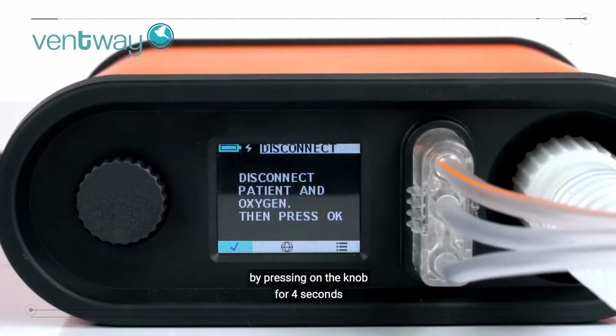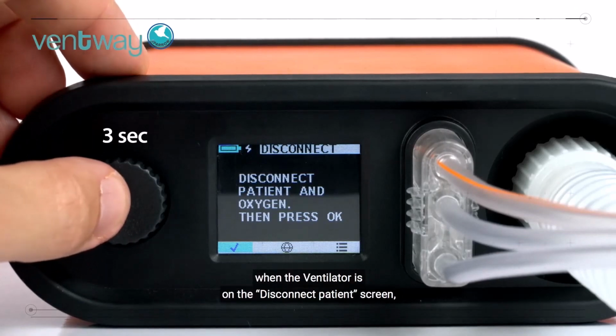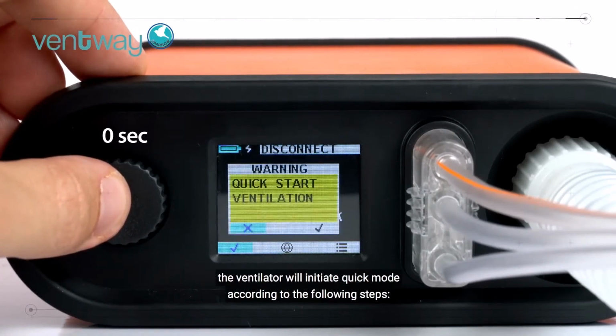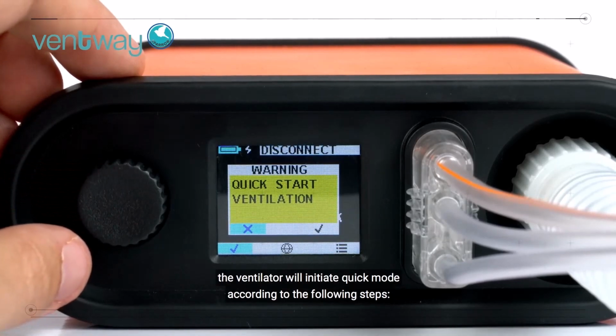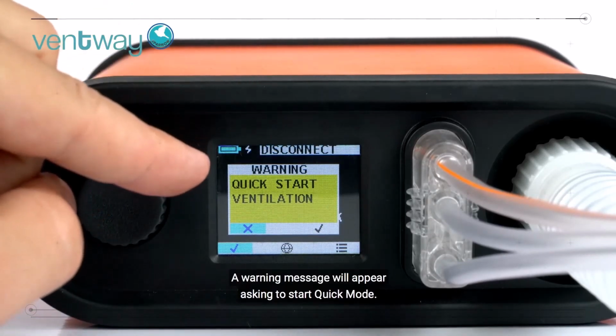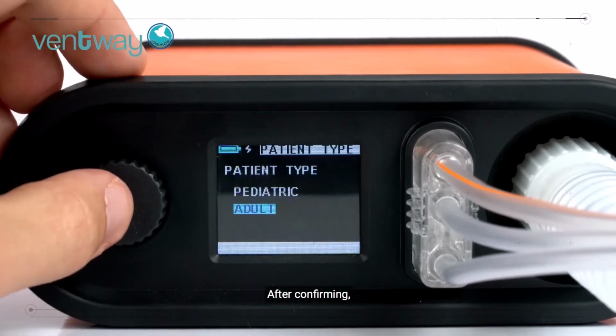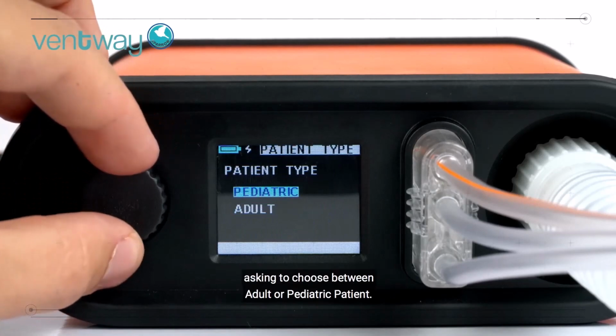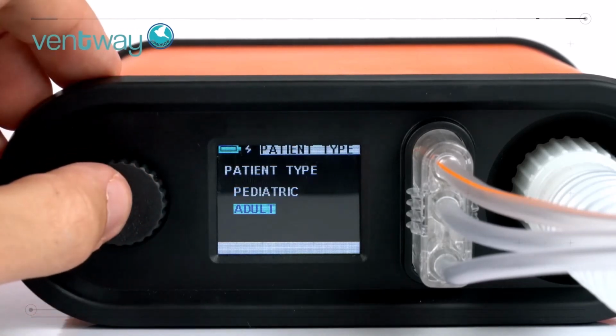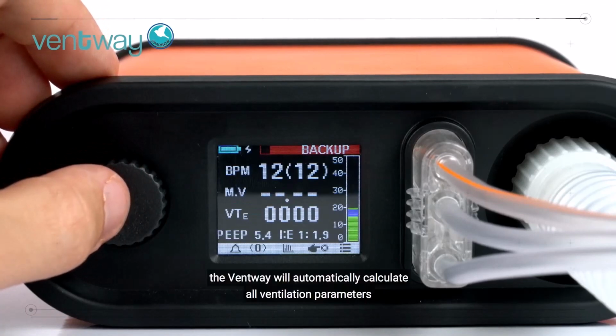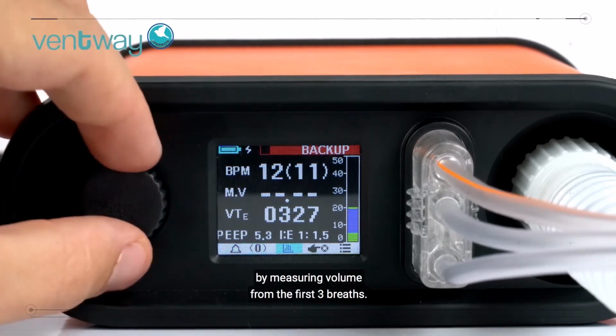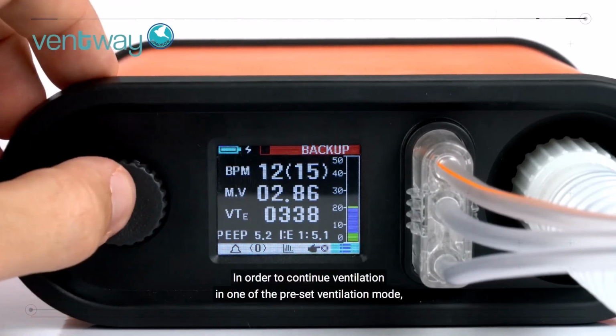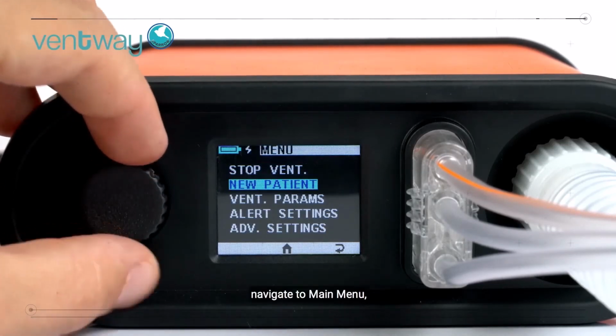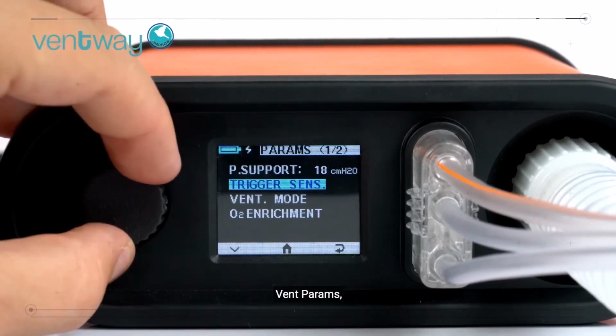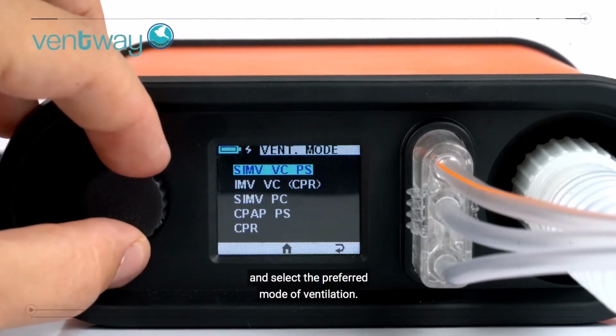Quick mode. By pressing on the knob for 4 seconds when the ventilator is on the disconnect patient screen, the ventilator will initiate quick mode according to the following steps. A warning message will appear asking to start quick mode. After confirming, the patient type screen will appear asking to choose between adult or pediatric patients. After choosing patient type, the Ventway will automatically calculate all ventilation parameters by measuring volume from the first 3 breaths. In order to continue ventilation in one of the preset ventilation modes, navigate to Main Menu, Vent Params, Vent Mode, and select the preferred mode of ventilation.